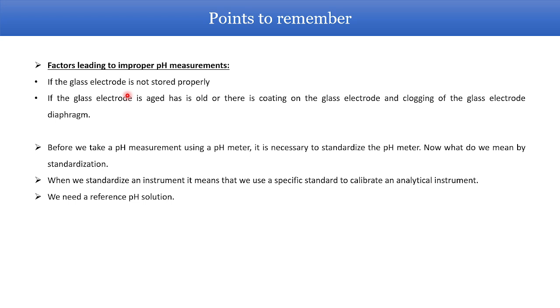First is that it will give you proper measurements. Second, it will avoid the cross contamination of the sample that you are using. So always do this. It's highly recommended. Number two is that you always need to standardize or calibrate your pH meter. How do you do this?